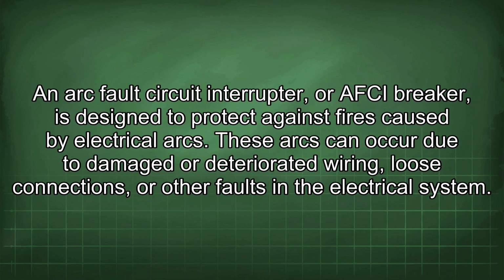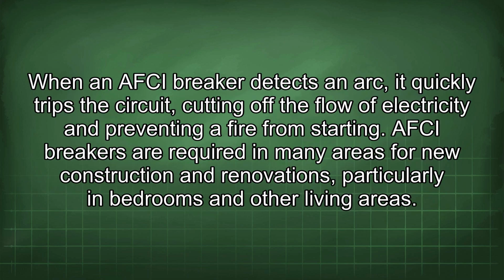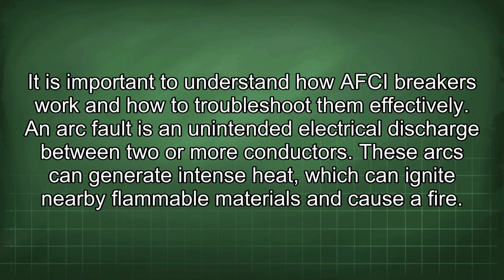An arc fault circuit interrupter, or AFCI breaker, is designed to protect against fires caused by electrical arcs. These arcs can occur due to damaged or deteriorated wiring, loose connections, or other faults in the electrical system. When an AFCI breaker detects an arc, it quickly trips the circuit, cutting off the flow of electricity and preventing a fire from starting. AFCI breakers are required in many areas for new construction and renovations, particularly in bedrooms and other living areas. It is important to understand how AFCI breakers work and how to troubleshoot them effectively.